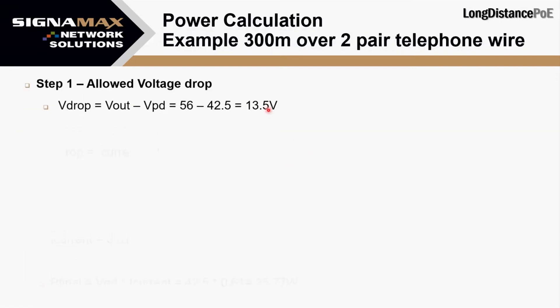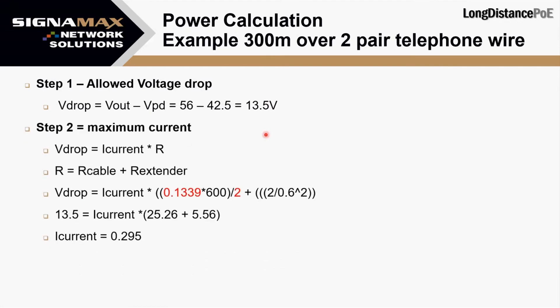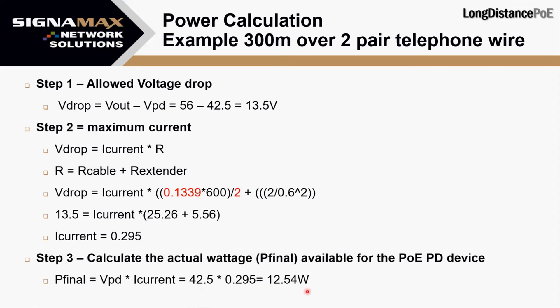Let's do another calculation — 300 meters over a two-pair telephone wire. The allowed voltage drop is the same 13.5 volts. The telephone wire resistance per meter is much higher than Category 6 — basically double. We multiply by 600 for round trip, but can only divide by two since it's two-pair. That gives a maximum current of only 0.295 amps, yielding just 12.54 watts. It's usable for low-powered devices, but compared to Category 6 at 500 meters giving 25 watts, we're getting half the power at less than half the distance. The cable medium is critically important.